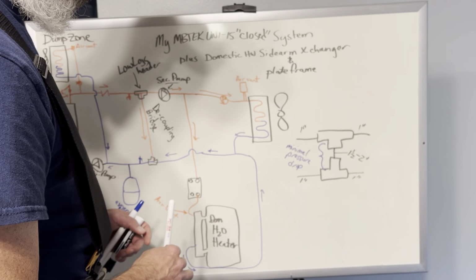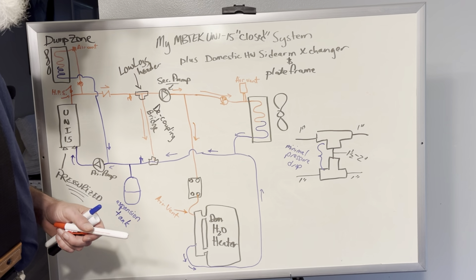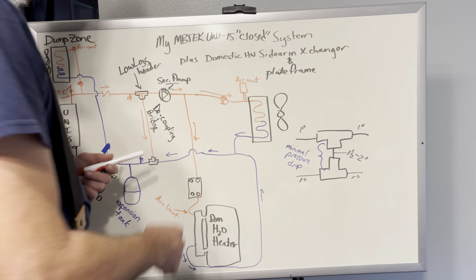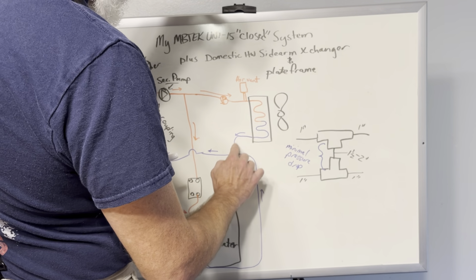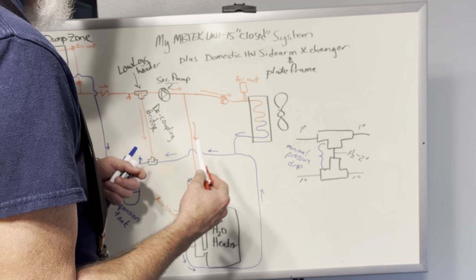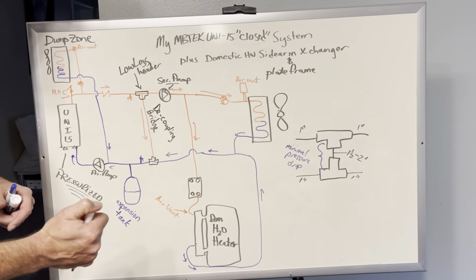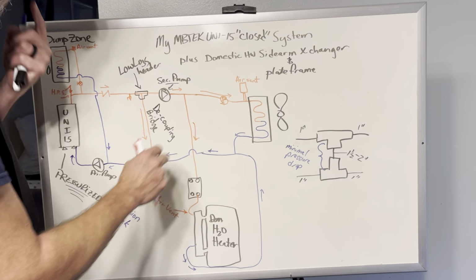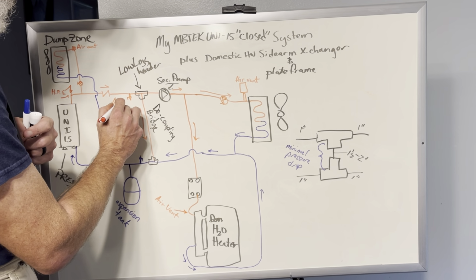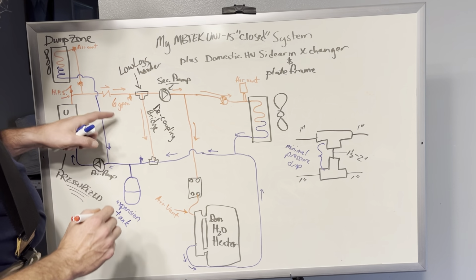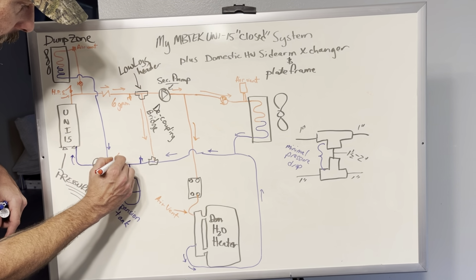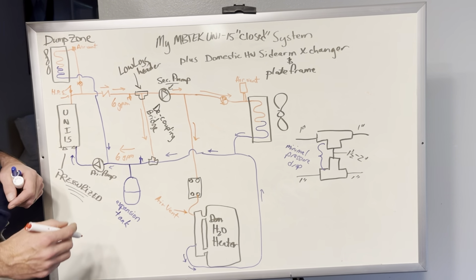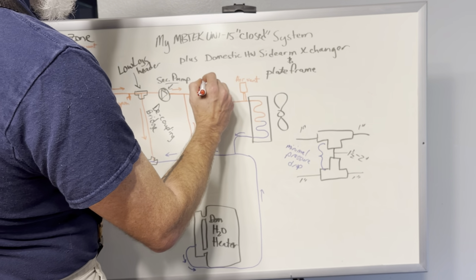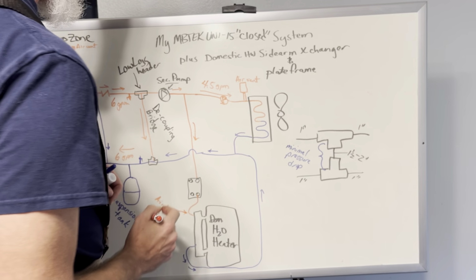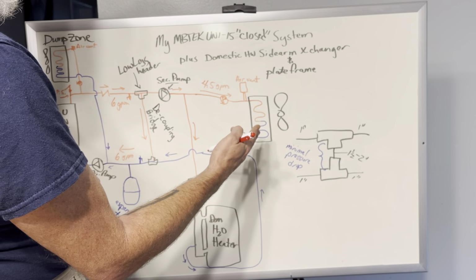Now, what happens when you have heat going on at the same time? Well, when my house thermostat says I need heat, it'll turn the fan on and it will open this valve. So flow will be right here in this direction. Let me just try to throw some general flows in there with both primary and secondary running. Let's say this is 6 gallons a minute here. Okay, so by default, that means this is 6 gallons per minute. This way, coming back, this may be, let's say, 4.5 going into the heat exchanger for my heat because the thermostat is asking for it.